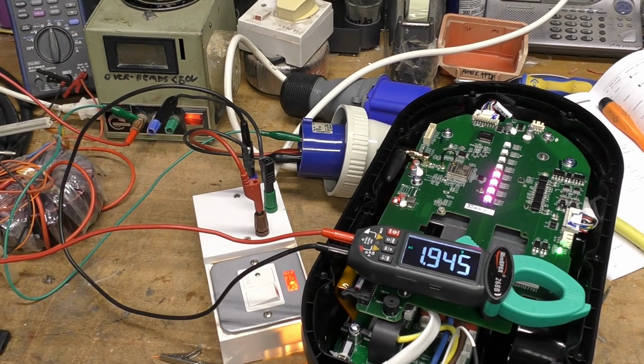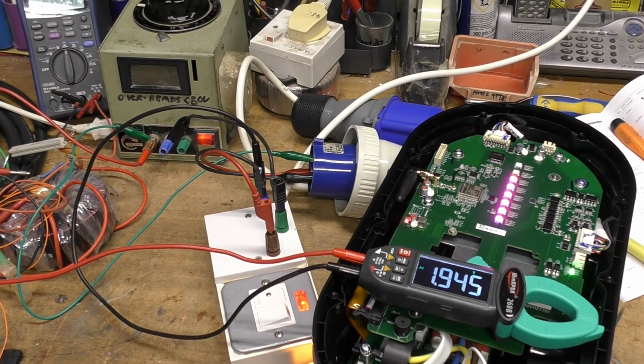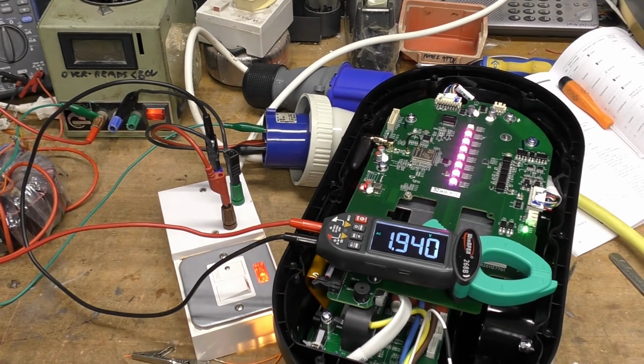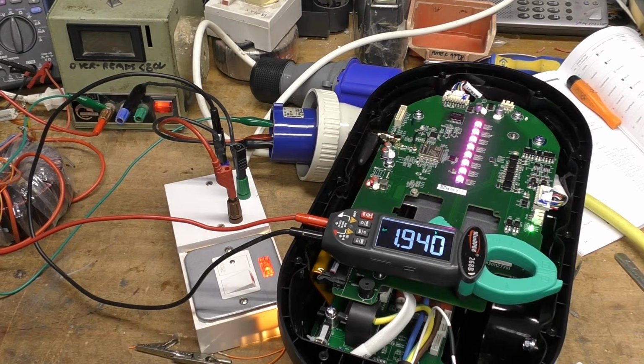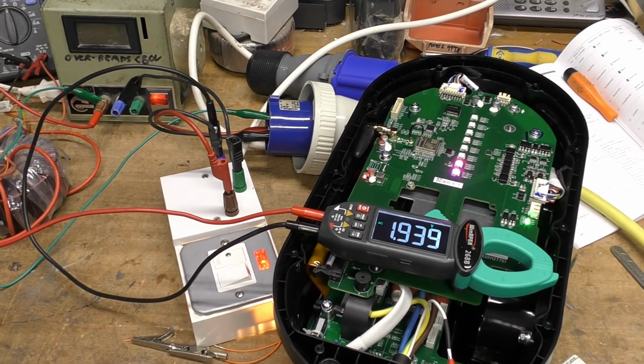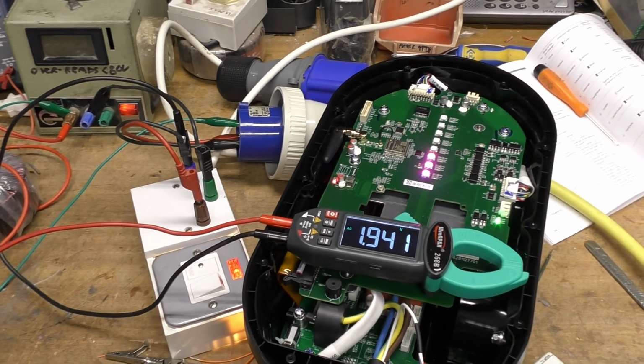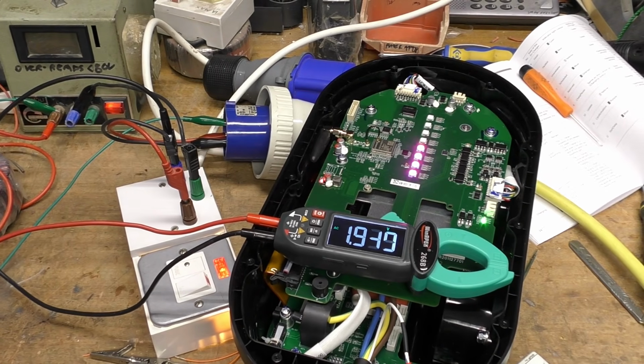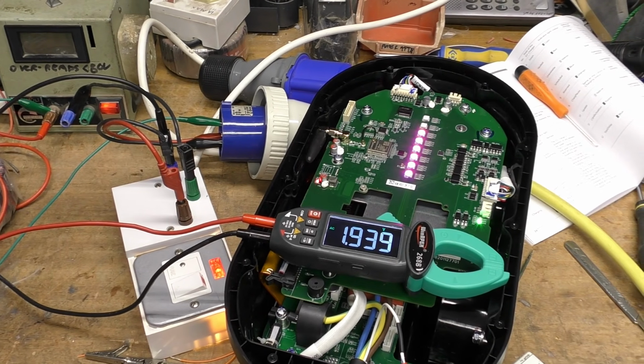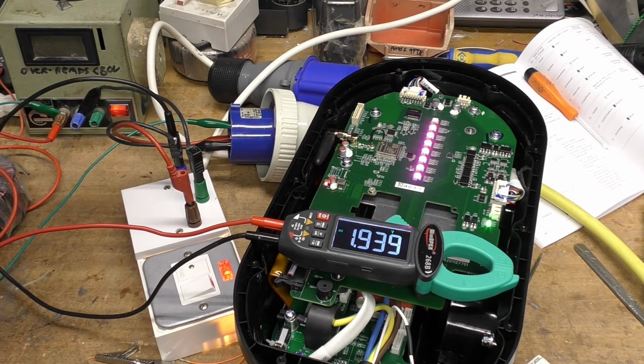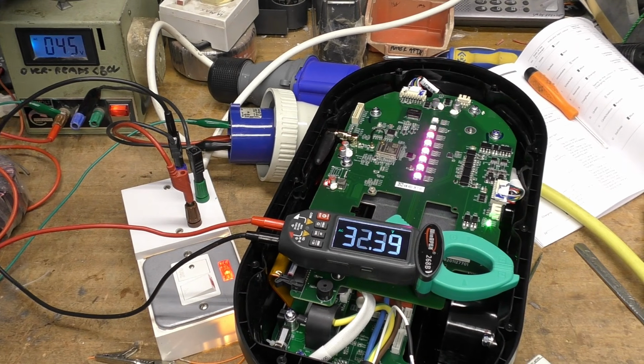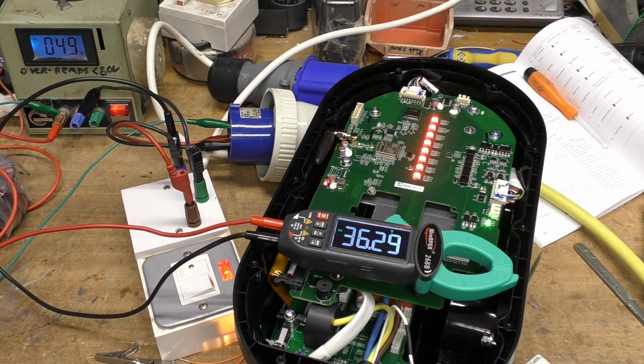Okay, I've now got a new setup. I'm running the variac through an isolating transformer and using that to inject a variable voltage between neutral and earth. Again, if the voltage between neutral and earth increases too much, then that should also trip out the PEN fault detection. So let's see what happens with that. That's tripping at about 35 volts, which is reasonable. Just see if that resets itself.